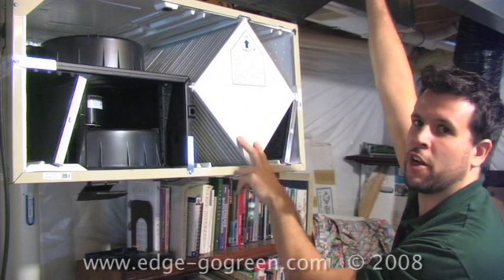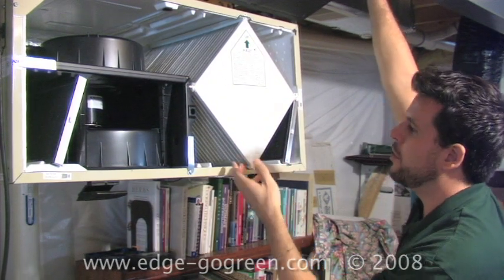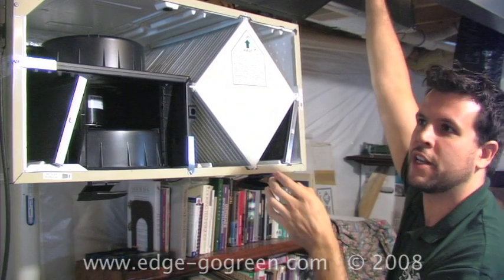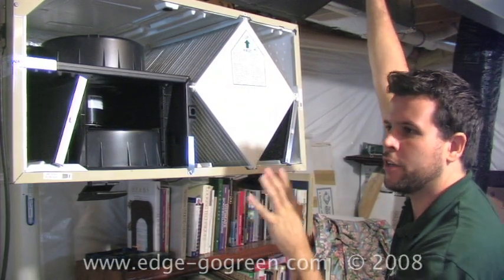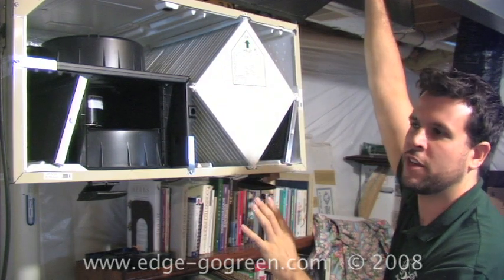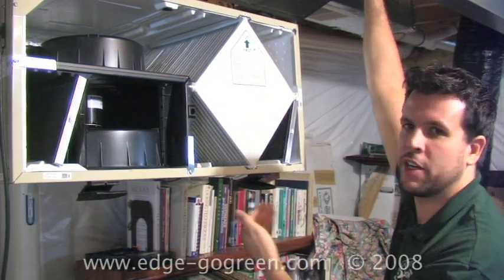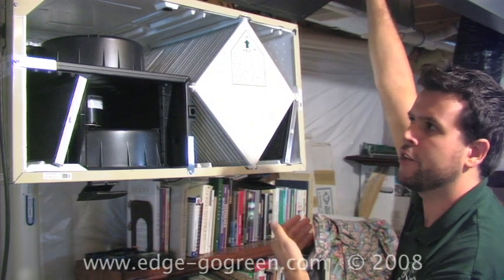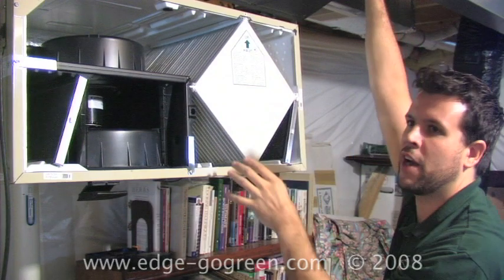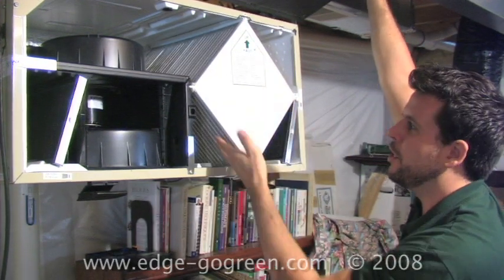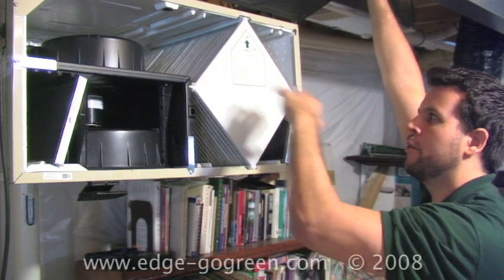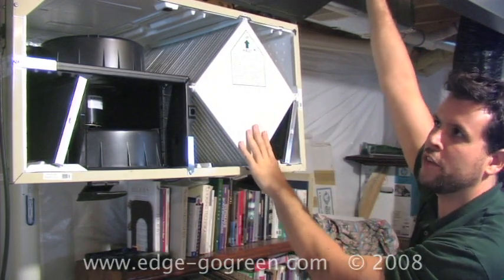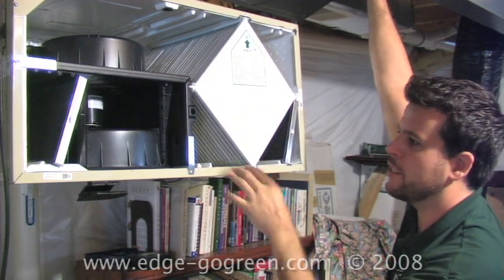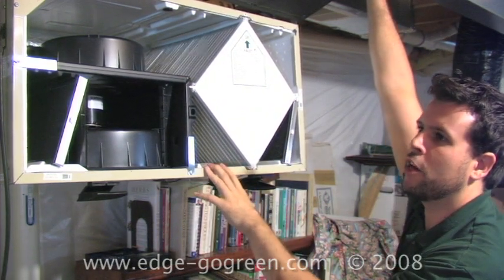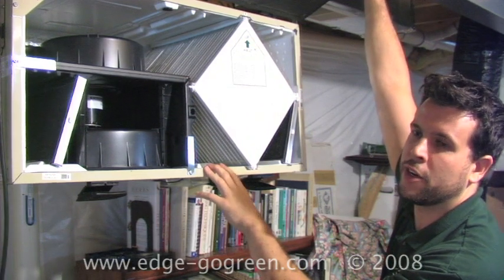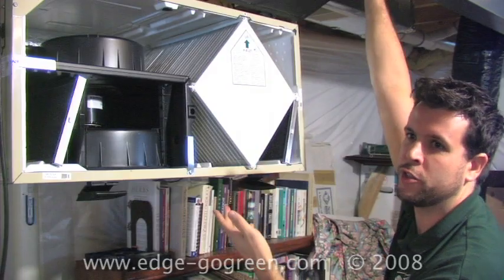Now the main portion of the ERV is what we call the heat exchanger. This is a couple hundred little metal fins that allow the air to transfer through conductive forces, heat specifically, and then some moisture. There's no actual exchange, no mixture of the two air supplies. So the stale air that's coming out of the house has no physical interaction with the air that's coming into the home. But these metal fins in the heat exchanger allow the outgoing supply to transfer about 80% of its energy to the incoming supply air. What that means is that even in the middle of the wintertime, you can be running the ERV and it's not going to dramatically impact your interior air temperature, because you're recapturing the majority of the energy.